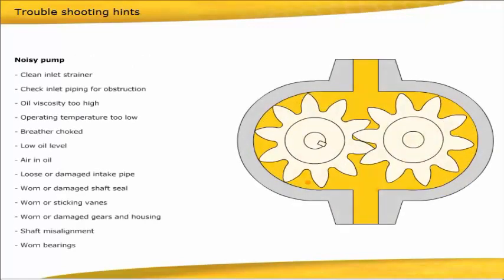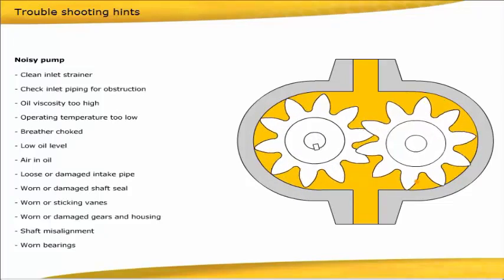Clean inlet strainer. Check inlet piping for obstruction. Oil viscosity too high. Operating temperature too low. Breather choked. Low oil level. Air in oil.